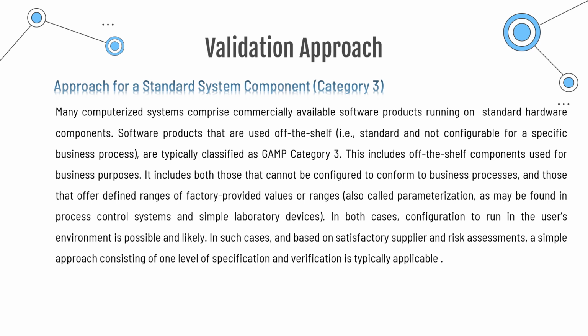This includes off-the-shelf components used for business purposes. It includes both those that cannot be configured to conform to business processes and those that offer defined ranges of factory-provided values or ranges, also called parameterization, as may be found in process control systems and simple laboratory devices. In both cases, configuration to run in the user's environment is possible and likely. In such cases, and based on satisfactory supplier and risk assessments, a simple approach consisting of one level of specification and verification is typically applicable.